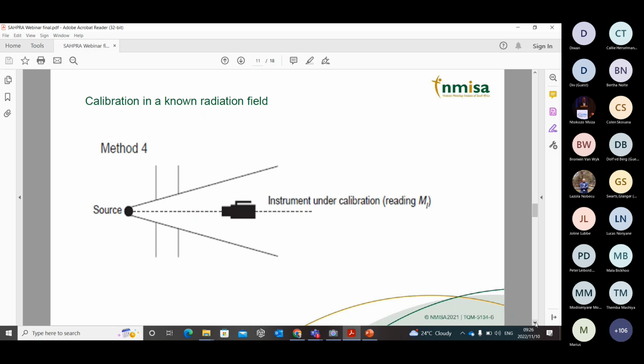So method 4, what is it? We are actually calibrating the instrument that is brought in to the lab using a known radiation field. What do we mean by a known radiation field? As I mentioned earlier, in calibration we're comparing the known to the unknown. So in this instance, the known will be the source, which means the amount of radiation that is coming out of the source.